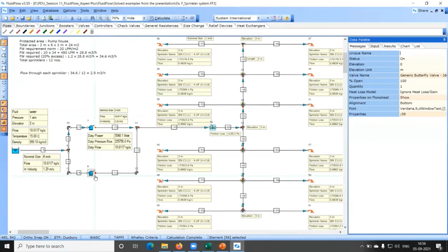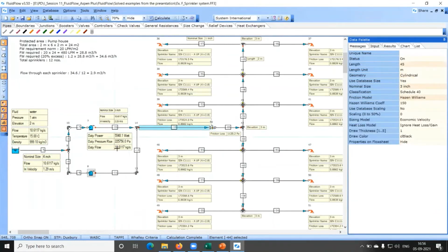no, it will not be working. It will be off, and a single jockey pump will be working, and of course there will be a minimum recycle line, and it will try to maintain some pressure in the pump discharge header. Let us say that pressure is, I'm just putting a number, say 5 bar gauge, right? So just imagine the small pump, the 3.5 meter cube per hour jockey pump, is working. This release valve is closed, and the system is able to generate a pressure of 5 bar gauge.